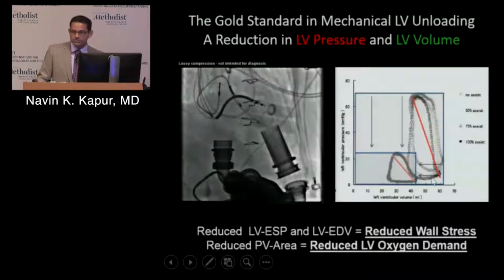And from the pressure volume loop perspective, this is a critical aspect of understanding these pumps. From a normal pressure volume loop, once you activate an LVAD, which is LV-to-aorta bypass, what you see is a significant reduction in pressure and volume within the left ventricle. And it's important to note also that under normal conditions, the pressure volume loop in the LV looks like a square. There's isovolumic contraction and relaxation, which are energy-dependent mechanisms, meaning that the LV has to work in order to contract and it has to work in order to relax. But once you put an LVAD in, you start to get a triangular configuration to the pressure volume loop. And to us, that's one of the hallmarks of unloading, because now you've taken away those energy-dependent mechanisms in the left ventricle, and now the pump has taken over the majority of stroke work of the ventricle.